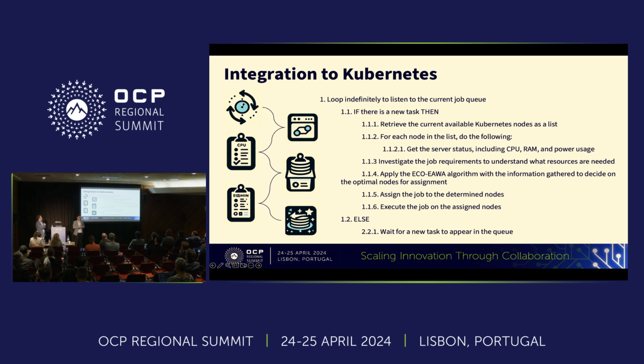So our Kubernetes, instead of the standard Kubernetes scheduler which only allocates the loads randomly, has all the tools we already discussed step-by-step being integrated into the new Kubernetes scheduler. What the system does is run a continuous loop: whenever there is a change on the IT load, the system asks the IT devices themselves, 'hey, what is your current status?' And it asks the cooling, 'hey, what is your current status?' Altogether, this system smartly allocates the workloads plus controls the coolant side, as a promise of a holistic cooling system in the data centers, which optimizes both hardware and software elements of the data centers.